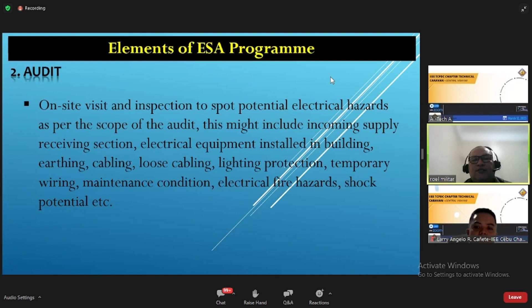Now, the actual audit - what we call the on-site visit and inspection - is meant to spot potential electrical hazards as per the scope of the audit. This might include the incoming supply, receiving section, electrical equipment installed in the building, earthing, cabling, loose cabling, lighting protection, temporary wiring, maintenance condition, electrical fire hazards, shock potential, and others. Notice that the scope of the actual visit is for inspection to spot potential hazards during this safety audit.